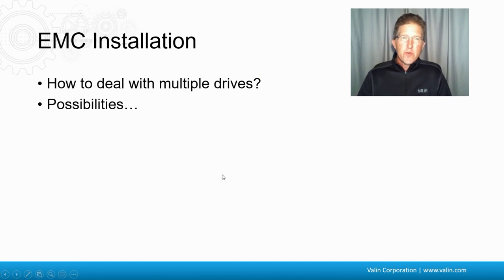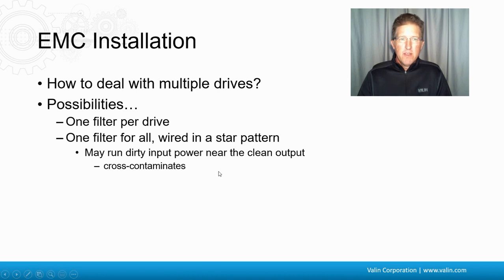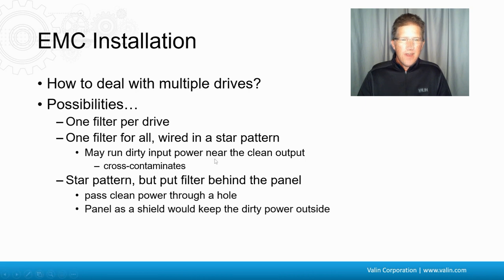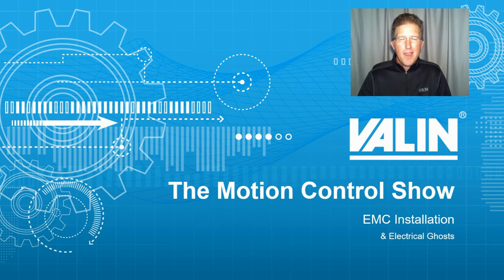If you have multiple drives, there are a couple of possibilities. One filter per drive can get expensive. Another option is one filter for all drives wired in a star pattern, but you may end up running dirty input power near clean outputs, which cross-contaminates. A good theoretical approach is wiring in a star pattern with the filter behind the panel, running clean power through a hole so the panel acts as a shield. Key dangers to be aware of: running high-power cables next to low-power cables — keep a significant gap or run them perpendicularly — and contaminating clean power with dirty. I've solved a lot of electrical noise issues just by doing a couple of these simple things.